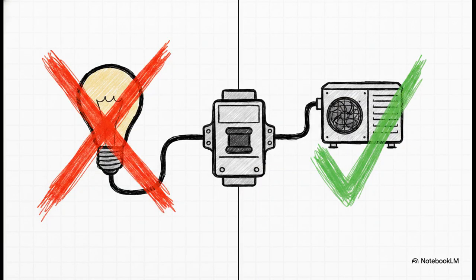And here is the absolute climax of this whole explainer. Under the special rules of NEC Article 440, running a number 12 wire on a 30 amp breaker is perfectly 100% code compliant. No joke. If you did this on a standard lighting circuit in your living room, huge code violation because number 12 wire is normally capped at a 20 amp breaker. But because the conductor meets the minimum circuit ampacity and the breaker doesn't exceed the nameplate maximum for this specific hermetic motor, this installation is exactly right for an AC unit.